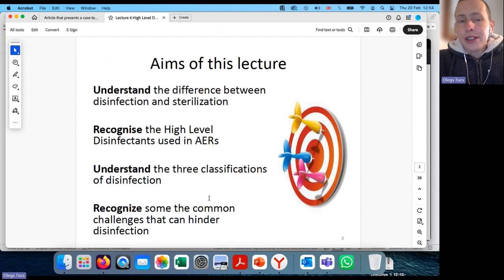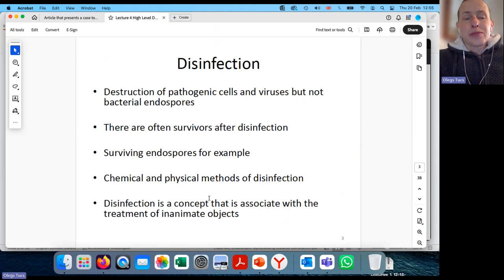And the idea is to start with the difference between disinfection and sterilization. We will talk about which chemicals are used in endoscope reprocessors, do a bit of a recap on low, intermediate, and high-level disinfection, and then disinfection challenges. So all that is in the next hour or so. Disinfection. What is it? Disinfection is destruction of microbes, but not all microbes. Destruction of pathogenic cells and viruses, but not all bacterial spores. And I suppose this is where we start, because there are going to be survivors after the disinfection.